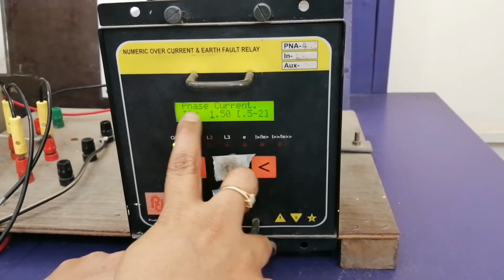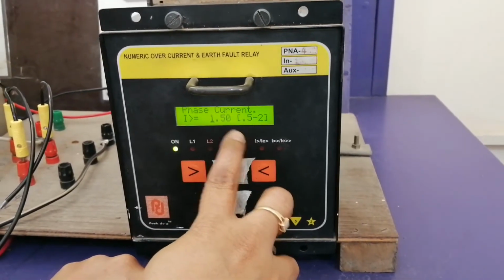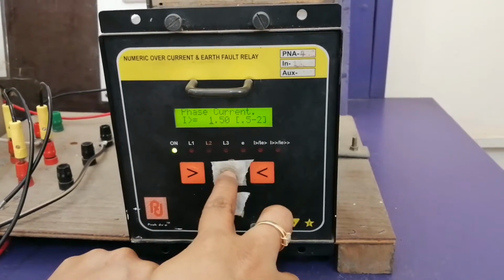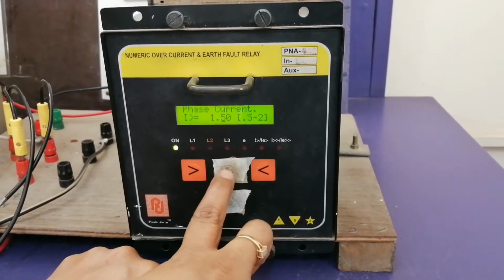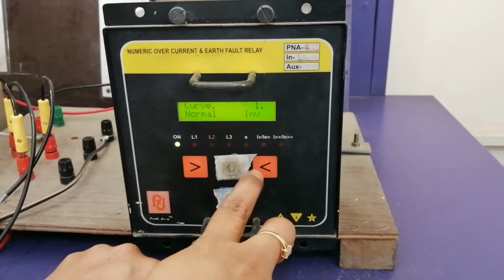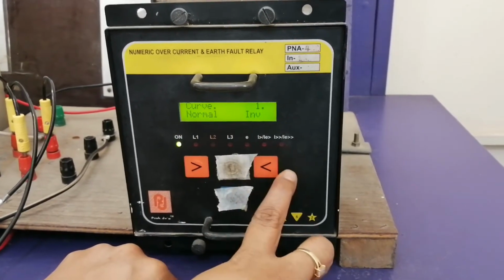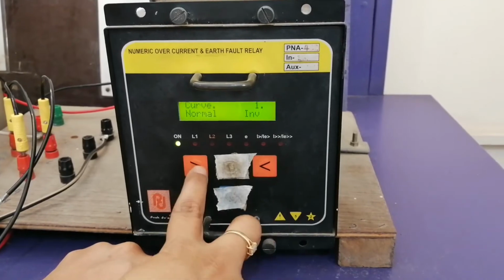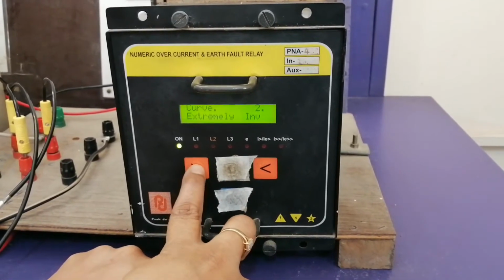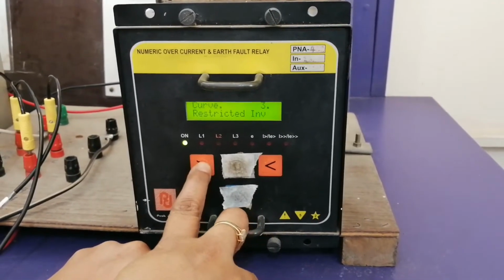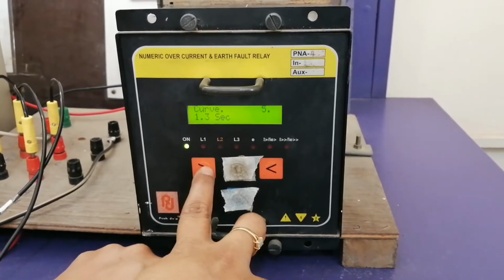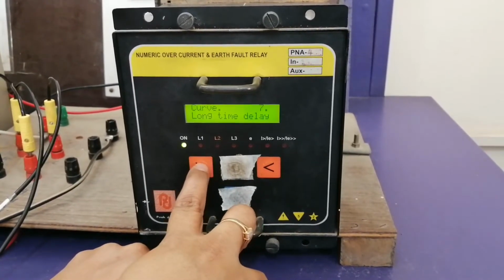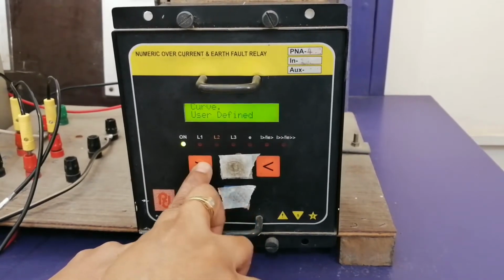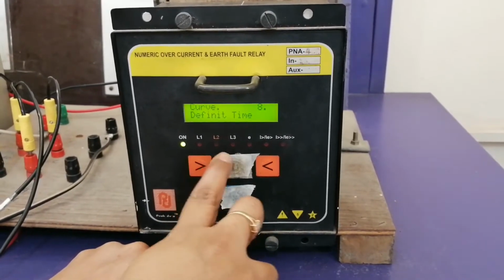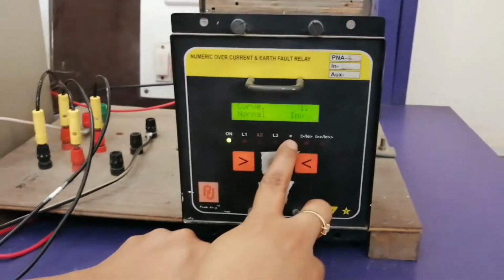Now see here, your phase current corresponds to your PSM. So I'm setting my PSM as 1.5, and see here, different curves can be plotted with this relay box. I can go for normally inverse curve, extremely inverse, restricted inverse, very inverse, 1.3 seconds, 3 seconds, long time delay, user defined, and definite time. But here I am going to plot normally inverse curve. So I am setting normally inverse curve.